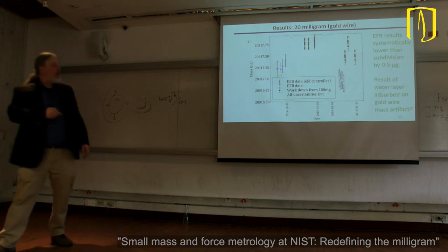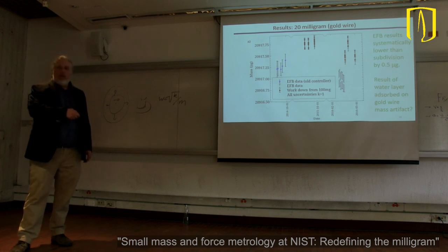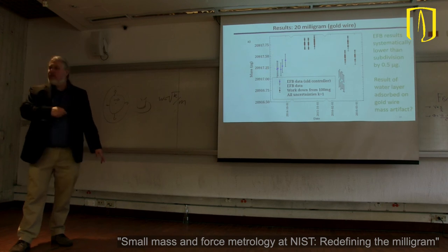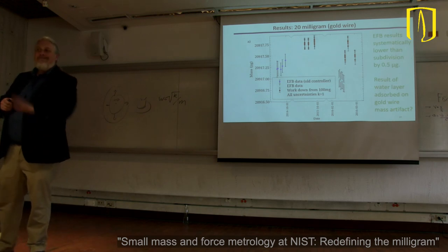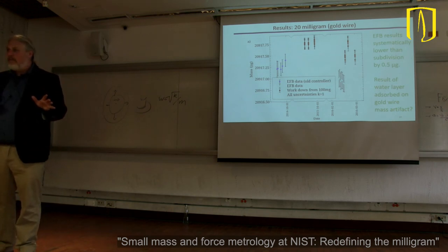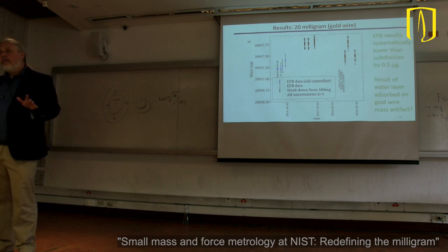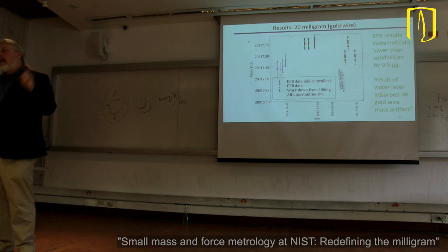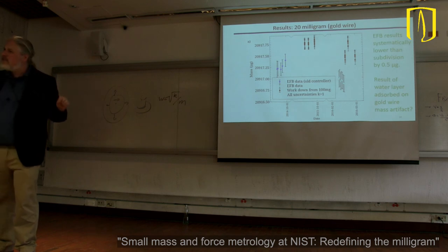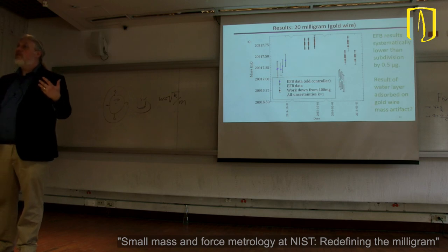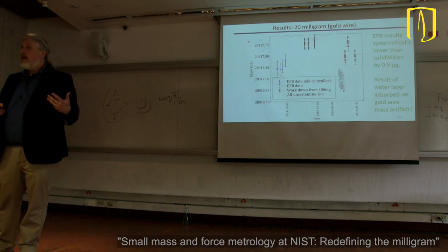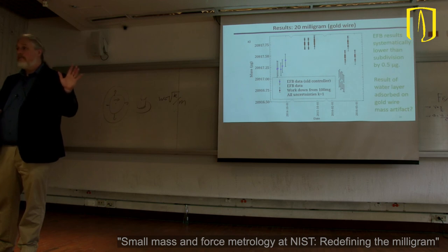Well, first of all, let me just say that for most purposes, we're looking at a change of 0.5 micrograms, and so usually it's not that big a deal, right? The problem is that you don't exactly know what it is because it changes, if that makes any sense, because the absorption of water changes with humidity, for example, right? You don't know what the effect is, and it can be very large.